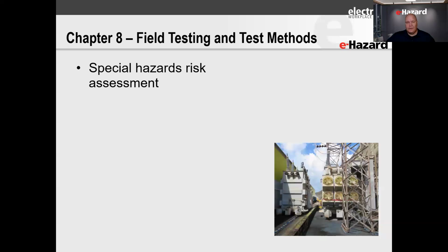Chapter 8 is where the rubber starts to meet the road. We get into what we call special hazards risk assessment, and this is really getting into looking at the condition of our equipment. When we go out there and start providing the tests that 70B requires, some of this stuff may be serviceable, some might not be serviceable and needs to be replaced, or maybe it has limited service, so we've got to restrict what we can do with it.